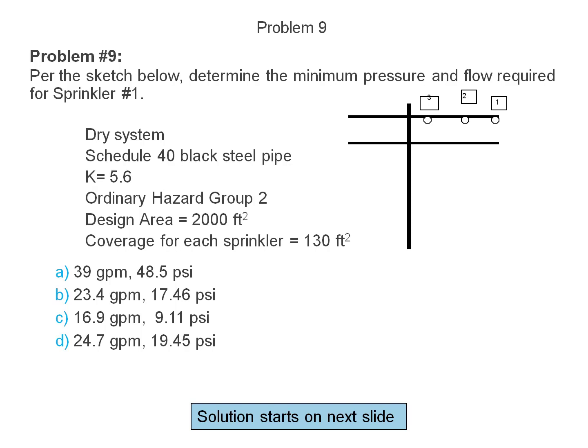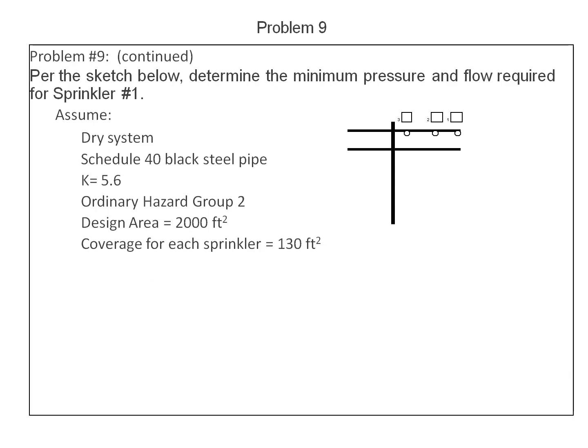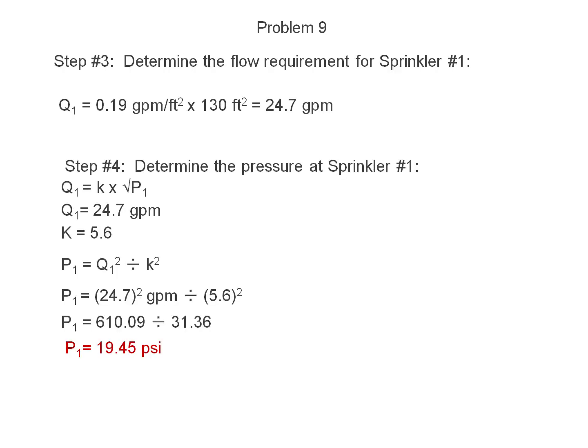The outline for this is a dry system, schedule 40 black steel pipe, the K is equal to 5.6, it's an ordinary hazard group 2, the design area is 2,000 square feet, and the coverage for each sprinkler is equal to 130 square feet. Is the answer A, 39 gallons per minute at 48.5 PSI, B, 23.4 gallons per minute at 17.46 PSI, or C, 16.9 GPM at 9.11 PSI, or D, 24.7 gallons per minute at 19.45 PSI.